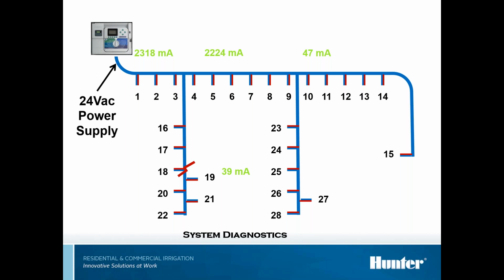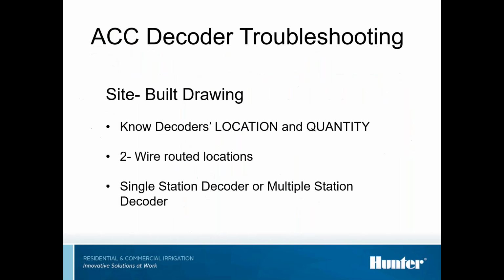At that one on that branch, it's 39. No, you're fine. There's still not a problem at that point. If you look at that number, it's 2,216. So your problem is probably going to be between 16 and 18. And then you check 17 out and it's 2199. So by process of elimination, you zeroed in on where your problem is at. Take it out, replace it, and you should be back up and running.